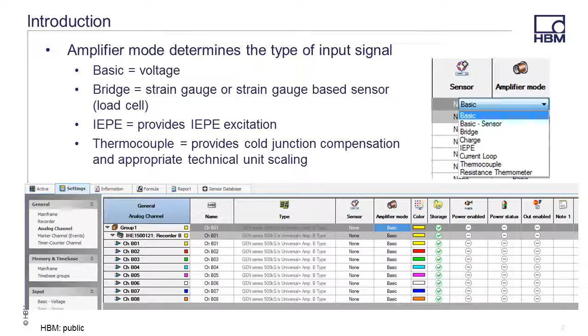Basic amplifier mode is a voltage input. Many of the options, such as Thermocouple, are self-explanatory. The basic sensor mode is used for sensors that require voltage or current excitation and don't fit into one of the other categories. The bridge mode is used for strain gauge sensors, quarter bridge, half bridge, or full bridge, and other bridge-type transducers, a load cell or force transducer, for example. IEPE mode is used for sensors that require IEPE excitation, sometimes also referred to as ICP sensors.